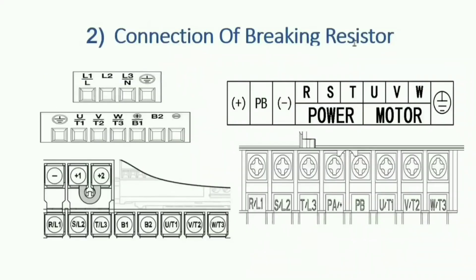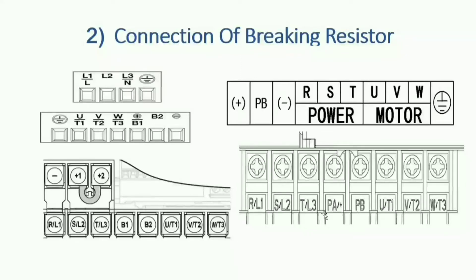Where do we connect the braking resistor in a VFD? I have shown you four different types of VFD terminal images. In this one, B1 is positive and B2 is the braking point, so we connect the resistor between B1 and B2. Similarly, in another drive it is between positive (+1) and PB. In another it is PA(+) and PB, and in another it is B1 and B2.